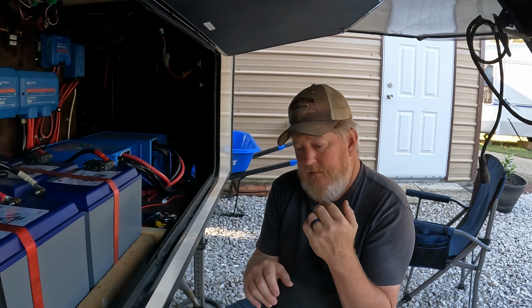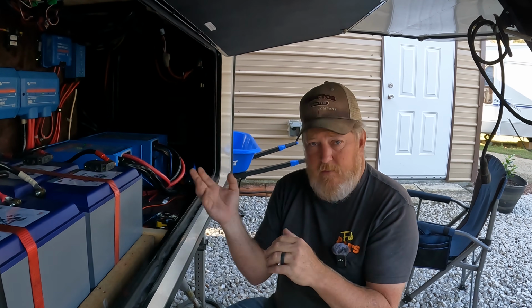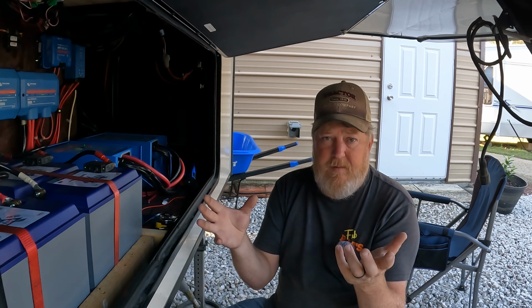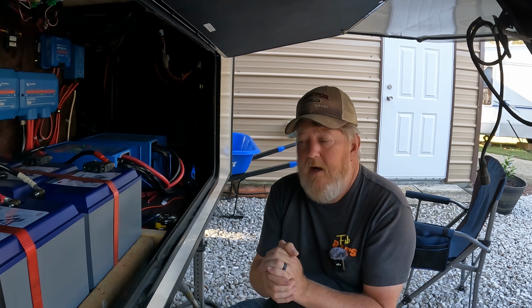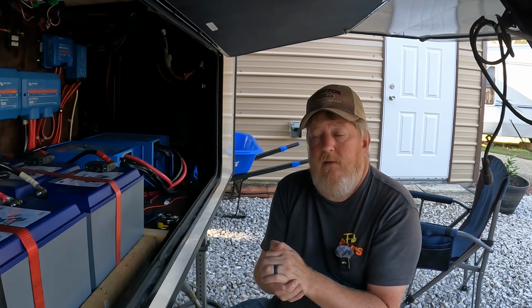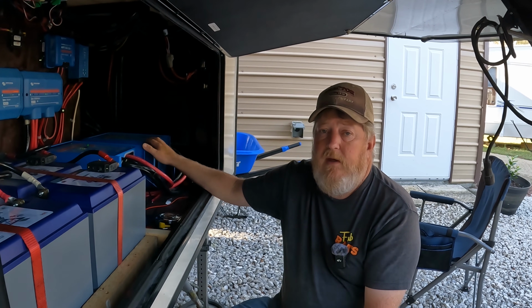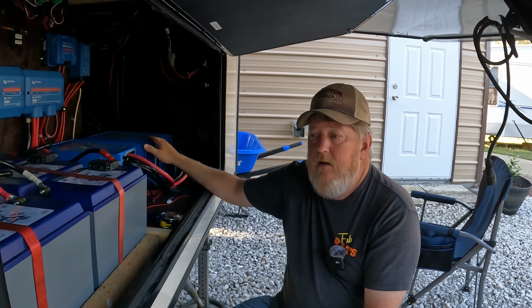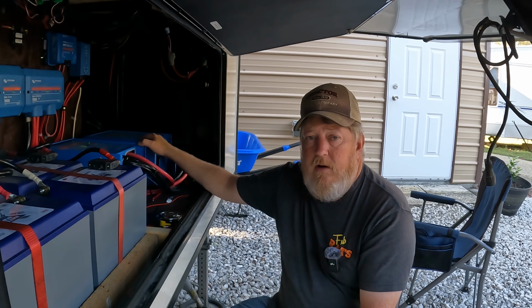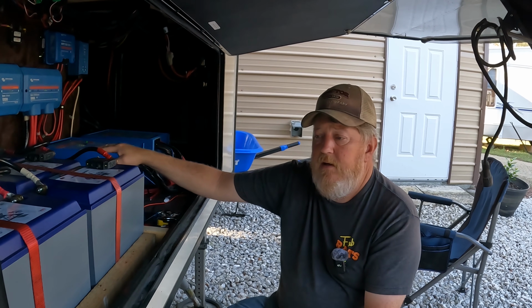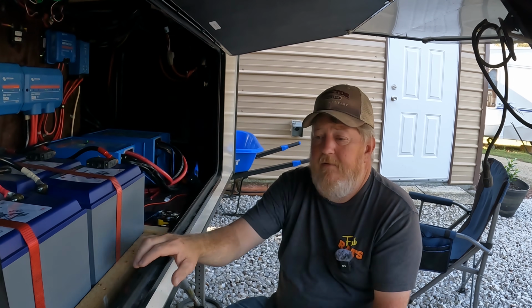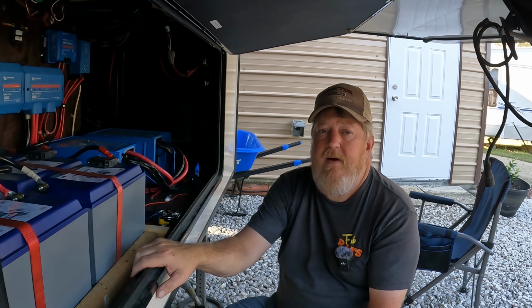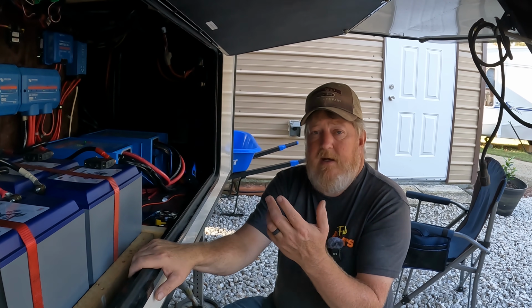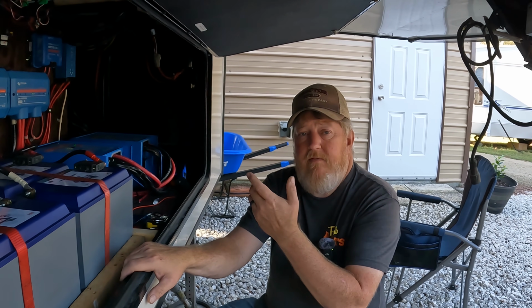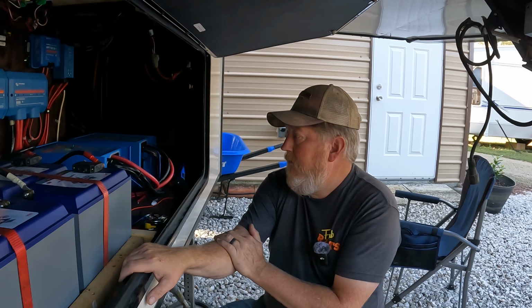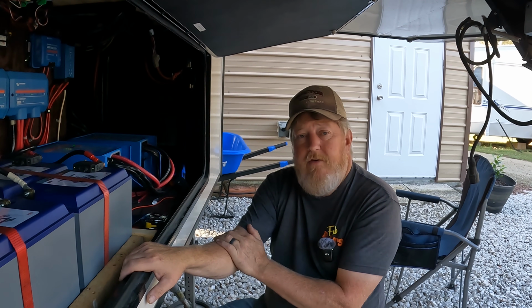We worked with an ambassador at Victron to try to tune it. We got it into UPS mode, I think they call it, still no love. So we added a second inverter and tried putting all the loads on one and the air conditioner on another. Nothing really seemed to matter. We still suffered that issue about 95% of the time when we disconnect at a campground. We've also had it overload a couple times just running.